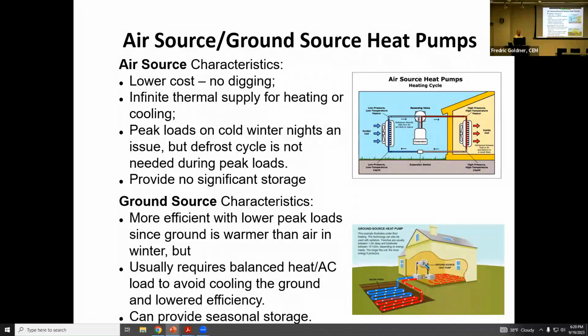You do not need a defrost cycle and the associated peak power additions when you're at a design point condition. Anybody know why or why not? It's very cold. It's like 0 degrees F. That's your design point situation. And there is no moisture in the air at 0 degrees F. So there's no condensation on the coils. So you don't need a defrost cycle.